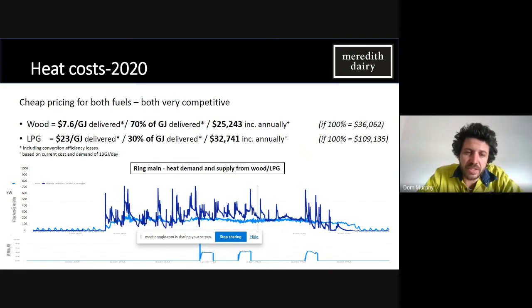Last year, so these are last year's figures, we were sourcing about 70% of our total energy from wood chips. And the reason we were only able to provide 70% of the energy was purely because of when we used that energy. We would have huge demand through the day. You can see from this graph down the bottom, the darker line is our demand on our circuit, and the lighter blue line is the supply from the wood-fired boiler. So there would be periods of the day where our demand would outstrip our supply. And unfortunately, we then would have to have LPG kicking in to make sure that we could continue production.